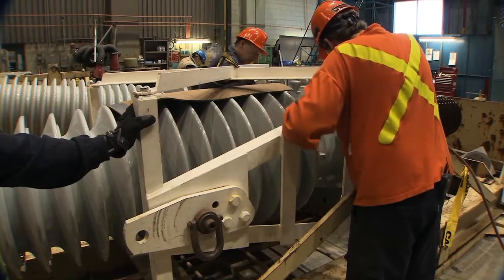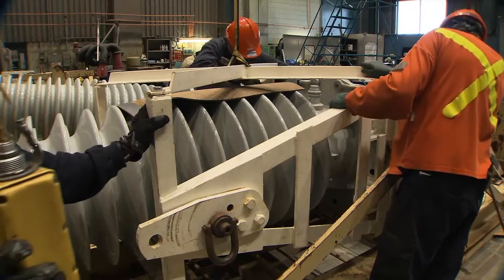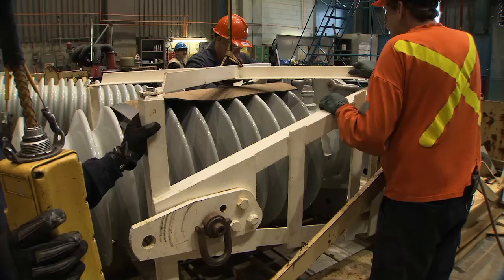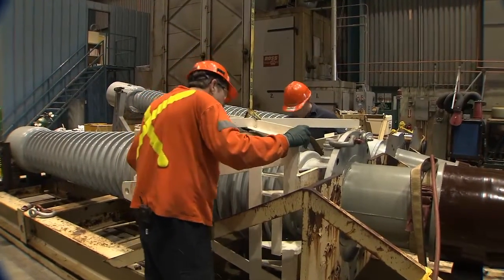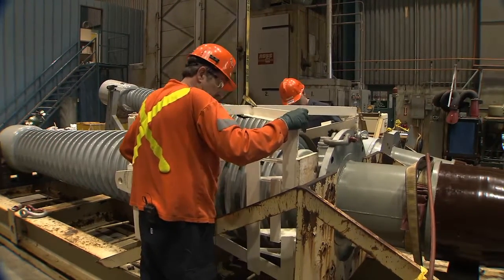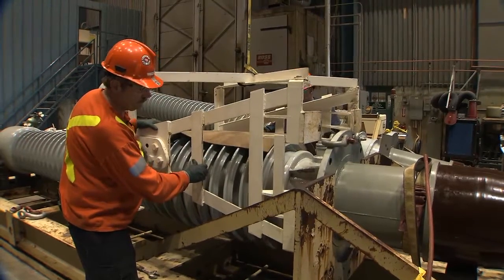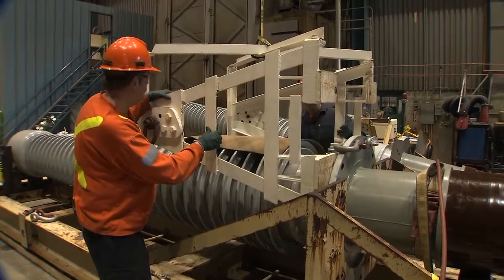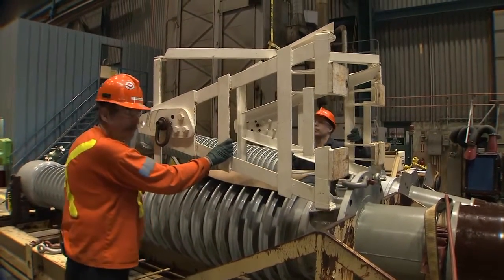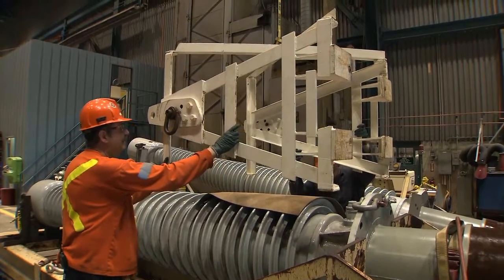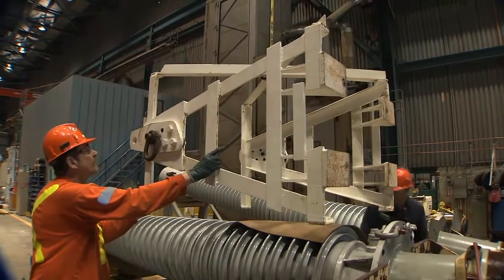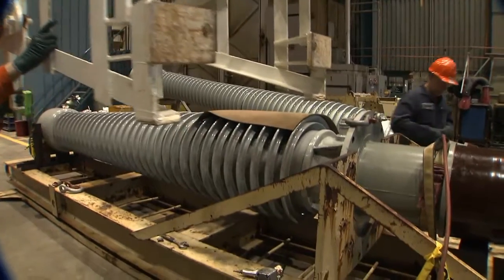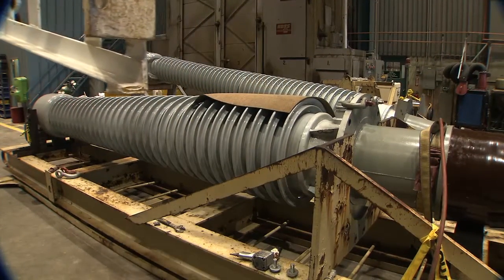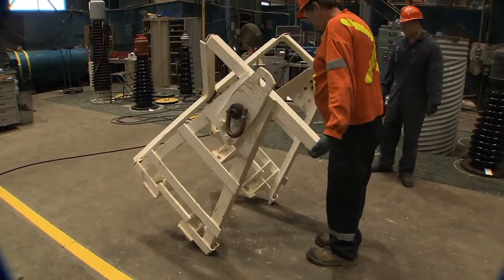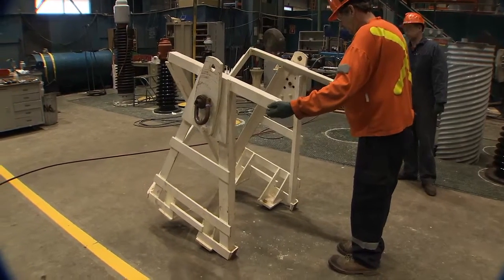Use a pneumatic air gun to loosen the bolts holding the lifting jig to the mounting flange of the bushing. Do you go up or down? Is this one? Straight up, Sam. Begin to slowly raise the lifting jig off the bushing. Team members on either side of the jig should guide it up to avoid the jig making any contact with the porcelain. Okay. Yep, got her. Move the jig into the concrete portion of the floor so that it stands on the 4 rectangular plates that were attached to the flange of the bushing.